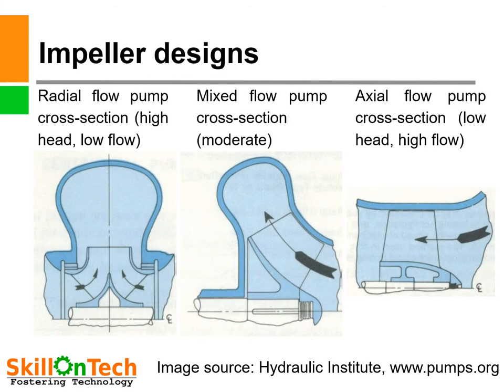Three pictures of three different kinds of impellers are shown. The first is a radial flow impeller, the second is a mixed flow impeller, and the third is an axial flow impeller. The radial flow impeller gives discharge perpendicular to the shaft, the mixed flow gives it diagonally at 45 degrees to the shaft, and the axial flow gives it axially. Radial flow impellers are used for high head and low flow; mixed flow for moderate flow and head; axial flow for low head and high flow.